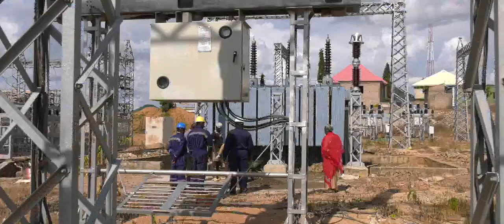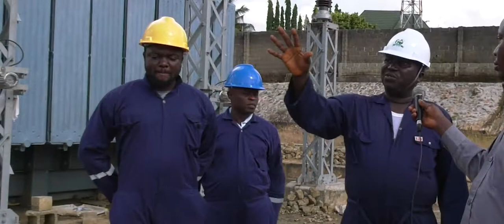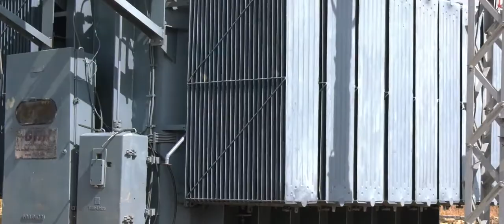Adebanji, who was in the company of other operations staff in their full safety wear, spoke of the impact the additional transformer will have in bulk power delivery. It will raise the substation capacity to 108 megawatts. We have two transformers, but due to high load demands, that was what brought about this baby project. This one is 45 MVA, which at maybe 80% loading will give us about 36 megawatts.